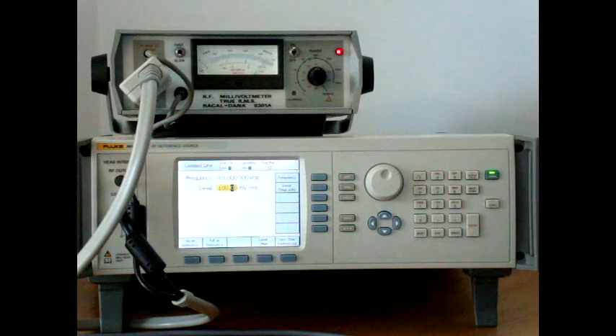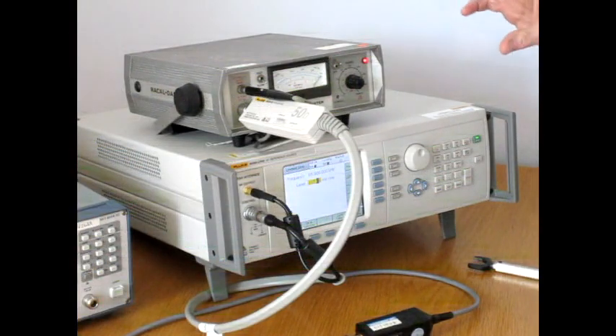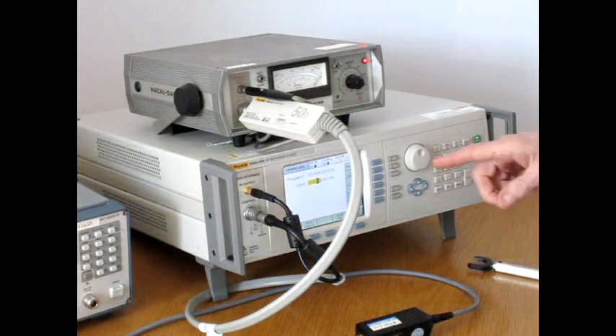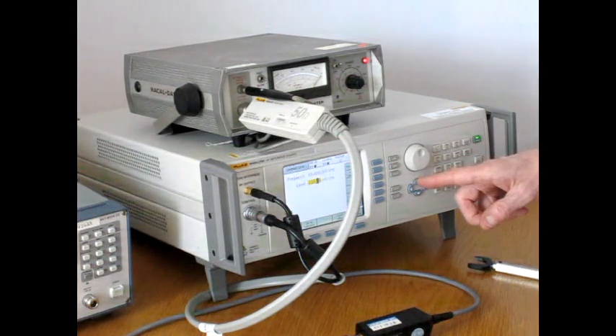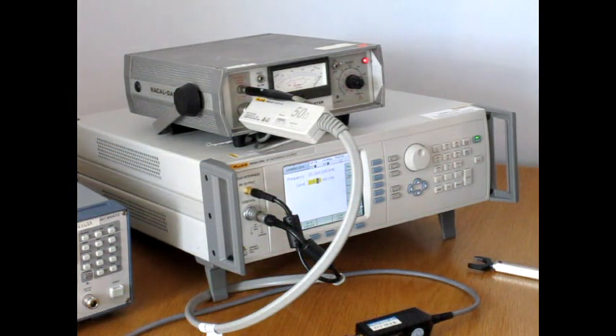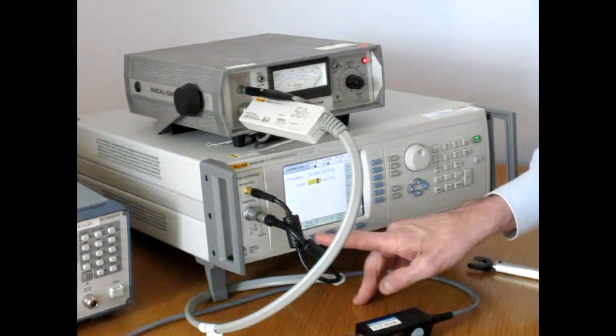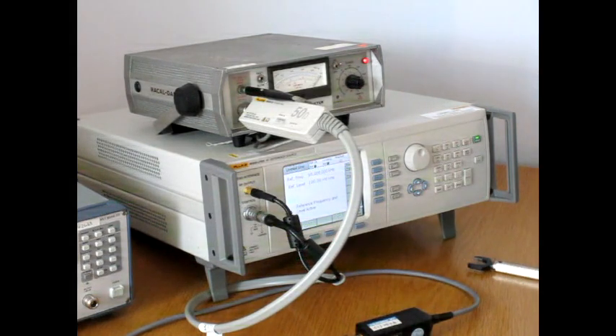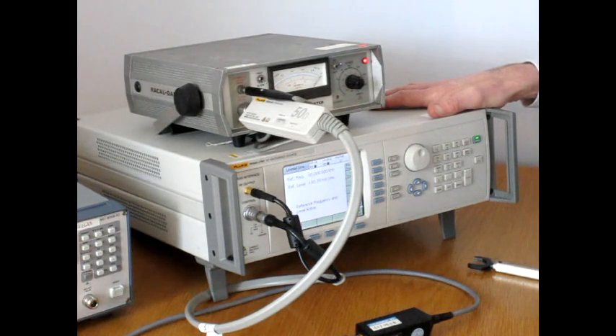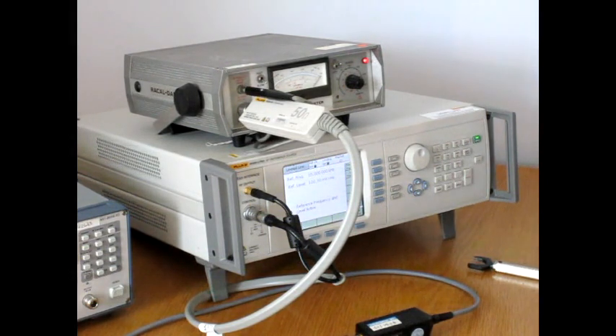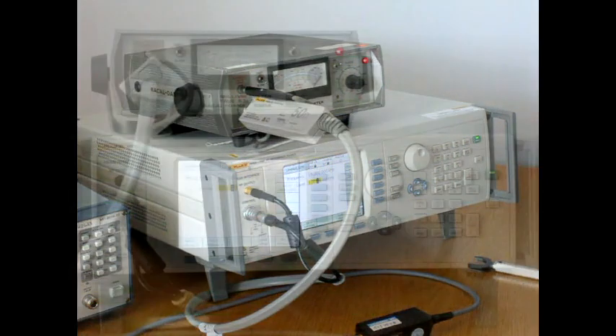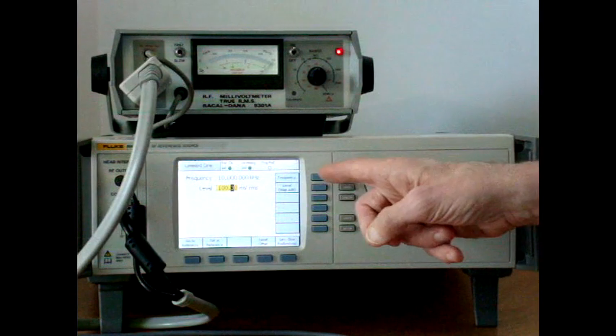Turn the output on, wait for the meter to settle, and we notice there is a small error. Now I would like to measure the frequency response with respect to this point, so I need to make a slight adjustment to the output until I read precisely the correct value of full scale, and I want to set that as a reference point for the frequency response. So I press the Set as Reference button, and the 9640 will remember that point as a reference in terms of level and frequency.